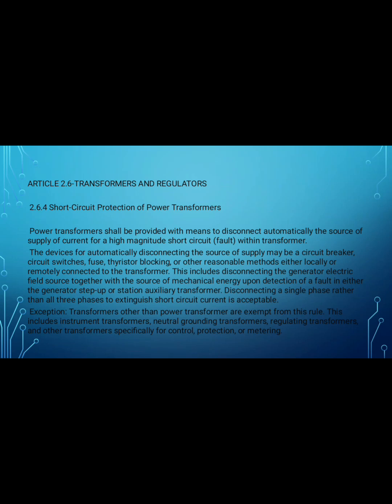Article 2.6 Transformers and regulators. 2.6.4 Short circuit protection of power transformer. Power transformers shall be provided with means to disconnect automatically the source of supply of current for high magnitude short circuit fault within the transformer. The devices for automatically disconnecting the source of supply may be circuit breakers, circuit switches, fuses, thyristor blocking, or other reasonable methods, either locally or remotely connected to the transformer.